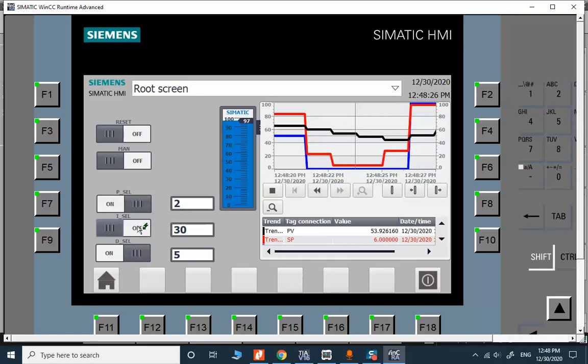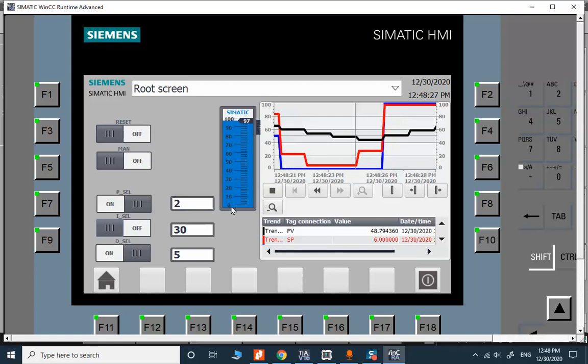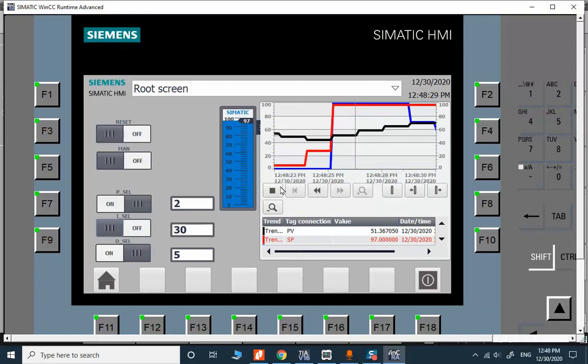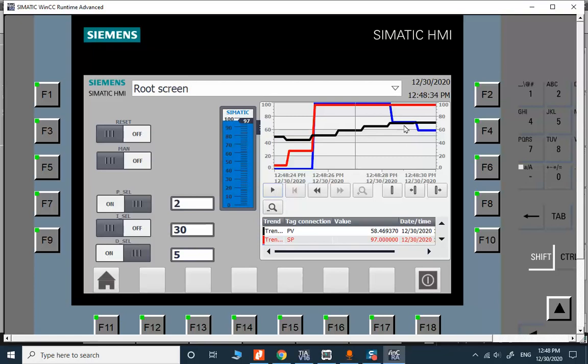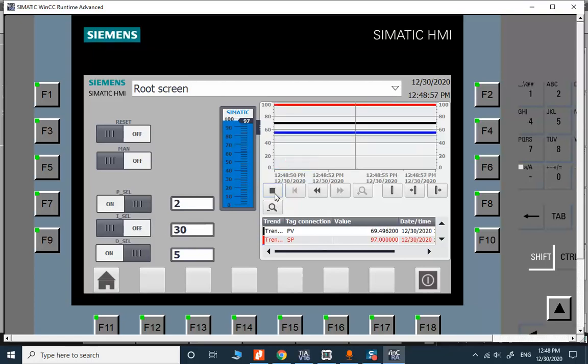Now let me turn it off. You can see that we're losing a huge amount of value from the control valve. The control valve is closing dramatically. It's very risky to do that when the controller is in automatic mode.